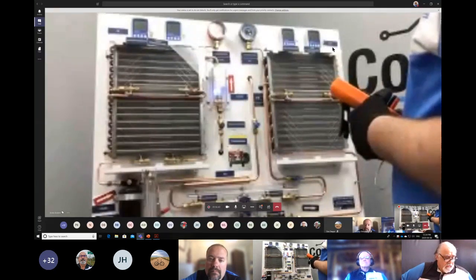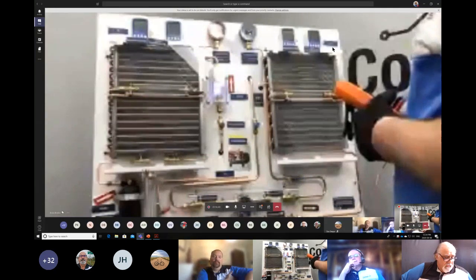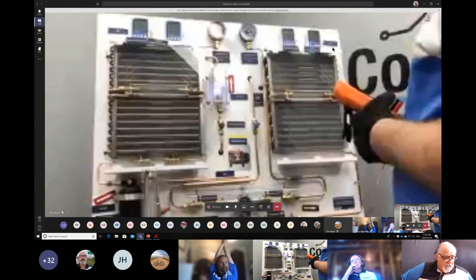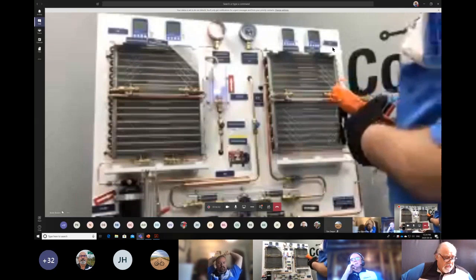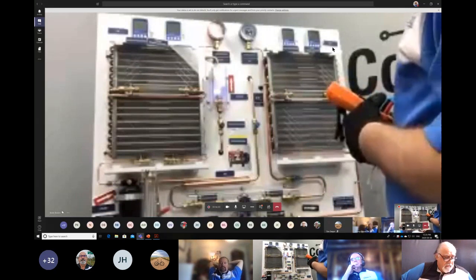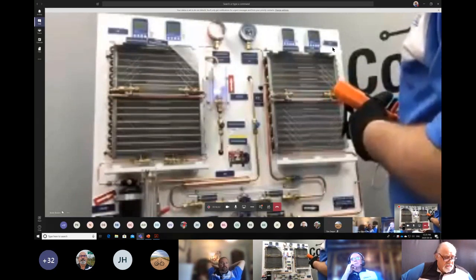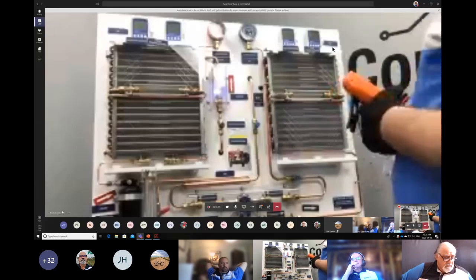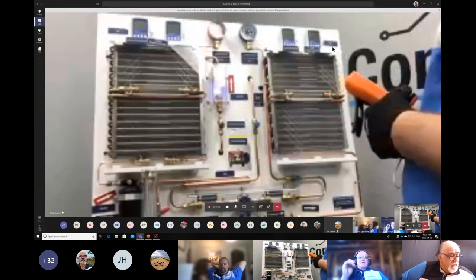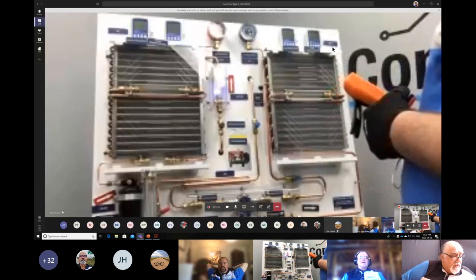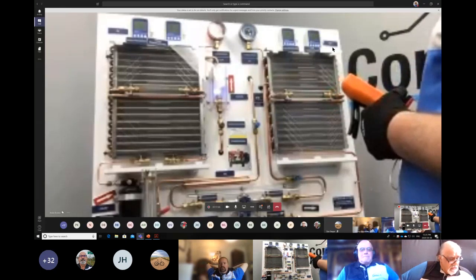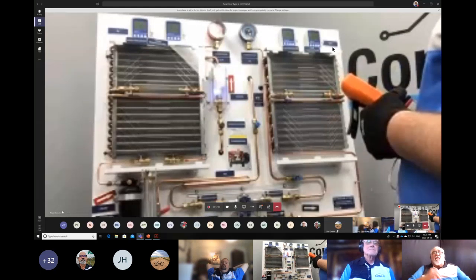And my temperature is going up. My temperature out, and what is it? I'm at 50.7 right now. But I'm at 35 psi at 50.7. So 35 psi is 36. So we're getting up in the 15, 16 degrees of superheat.